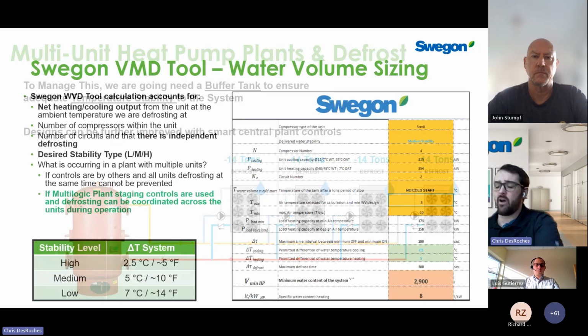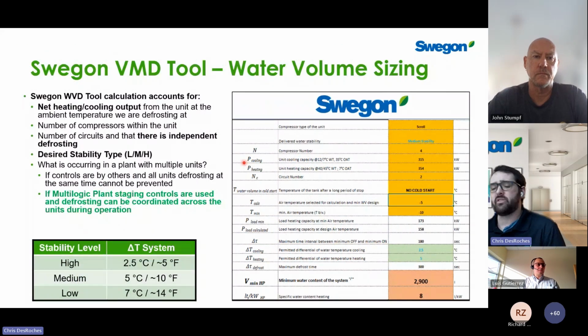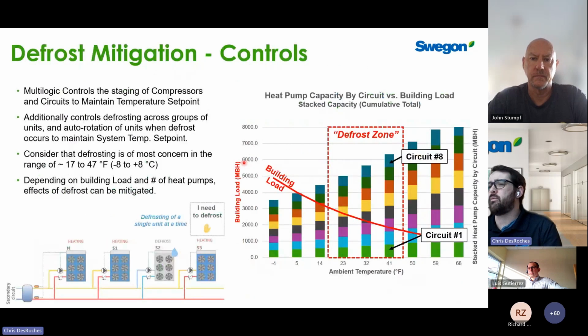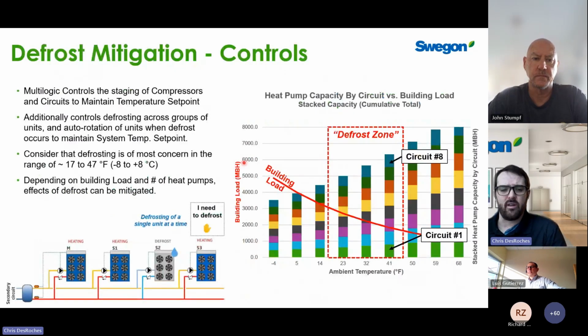So when we do a calculation for you, we don't just give you a basic rule of thumb. We'll look at this on a job by job basis. We'll look at the adjusted heating or cooling capacity that we want to get from the units at the condition that we're concerned about for defrosting, and we'll calculate it based on a certain stability for you. So we'd recommend a medium stability, which is sizing your volume such that in the worst case, when defrost is happening, we only see a temperature drop of 10 degrees Fahrenheit. So we'll look at this in depth with you, and there's a lot of sophisticated things.